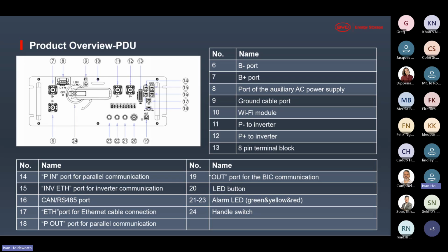or your bus bars, your rotary handles, your rotary switch, which is number 24, and your on-off button, which is number 20. It's always best to only turn your rotary switch when the batteries are off. So the little on-off switch there, you turn your batteries off and then you rotate your switch. It's always best to turn that switch either to off or to on when the battery is off. And you can turn the battery off with the little number 20.